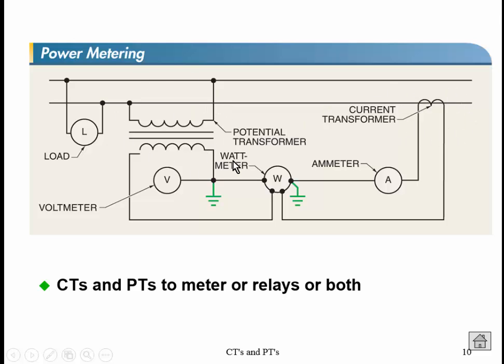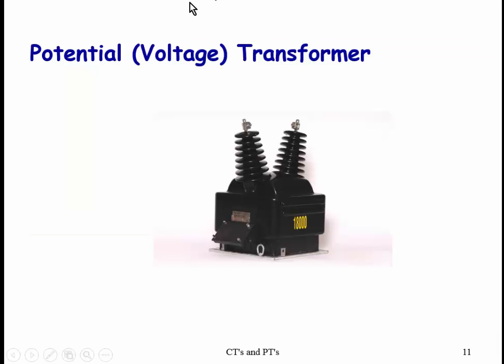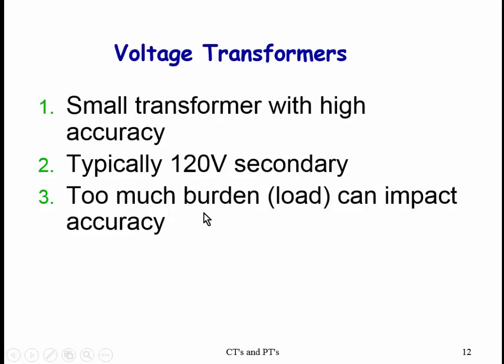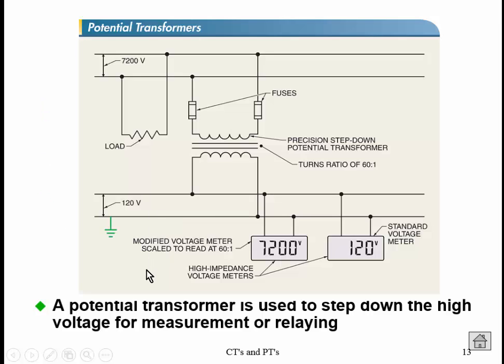Potential transformers are really just transformers like we're used to. The only difference is they're high accuracy, and they're really not meant to run lights and motors and things. They're meant just for measurement and for relaying. So that's what we're talking about here, a voltage transformer, which we call a PT, potential transformer. And they're just very accurate small transformers, and they're really not used for loads.